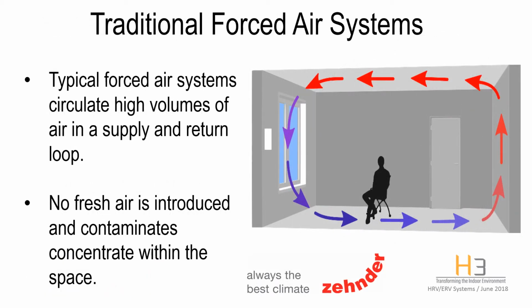Before we get into the HRV conversation, it's important that we distinguish between ventilation and conditioning. Traditional forced air systems do not provide ventilation. They essentially circulate the same pollutant-laden air in a loop. These systems provide thermal conditioning, but certainly not fresh air. If someone has a cold or a virus, the system could potentially spread it throughout the building. In the past, with leaky buildings, we got by with these systems, but with tighter, more efficient structures, we need to deliver a substantial source of fresh air.